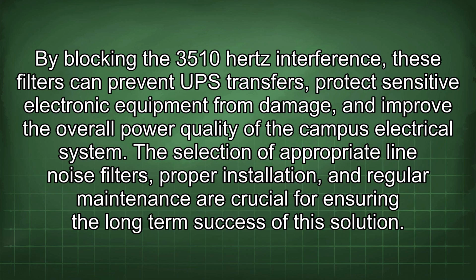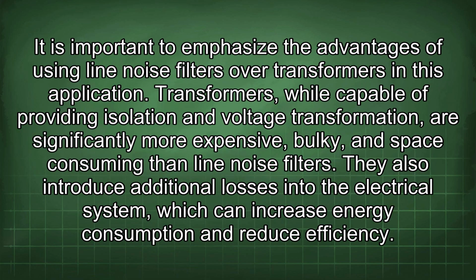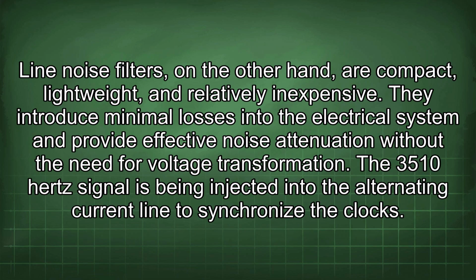The selection of appropriate line noise filters, proper installation, and regular maintenance are crucial for ensuring the long-term success of this solution. It is important to emphasize the advantages of using line noise filters over transformers in this application. Transformers, while capable of providing isolation and voltage transformation, are significantly more expensive, bulky, and space-consuming than line noise filters. They also introduce additional losses into the electrical system, which can increase energy consumption and reduce efficiency. Line noise filters, on the other hand, are compact, lightweight, and relatively inexpensive. They introduce minimal losses into the electrical system and provide effective noise attenuation without the need for voltage transformation.